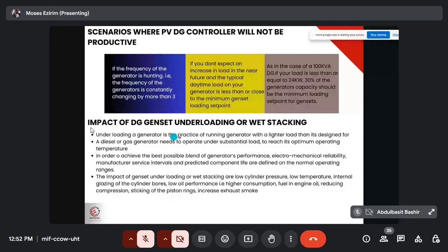This way, no, you are not helping the generator. Now, in order to achieve the best possible blend of generator performance and electromechanical reliability, manufacturer service intervals and predicted component life are determined on a normal operating range.